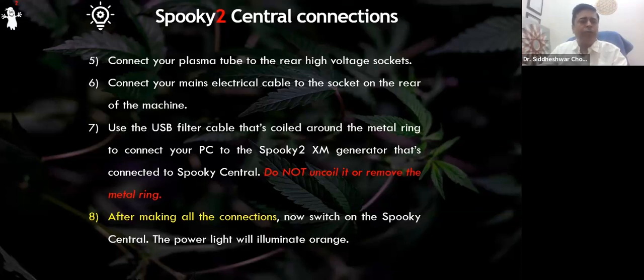Please make sure you connect your generator such that you have the metallic ring - these cables are called the USB filter cables. Make the connection so the filter cable is closer to the generator. Do not uncoil these filter cables or remove the metal rings - don't play with those. Some people forget these filter cables are meant for the plasma modality and mistakenly use their generator's normal straight cables to connect to the plasma unit. That is a big no - don't do that. We'll discuss later why these filter cables have been provided.